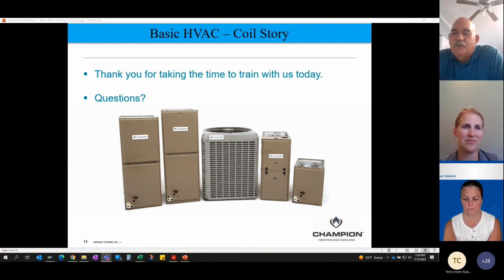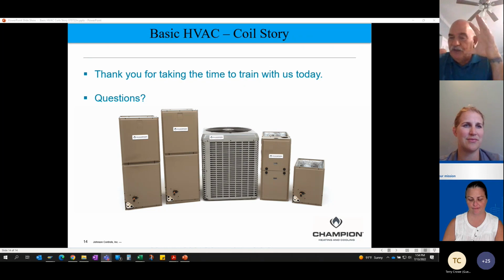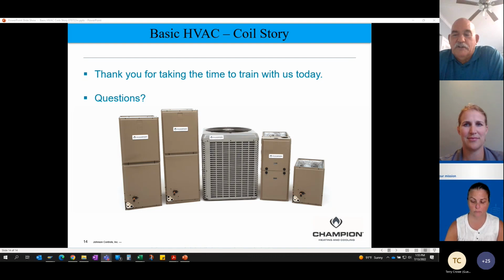Spine fin coil was invented in 1959, and General Electric started winding it on special machines down in Tyler, Texas, and they still use those machines. So this technology has been around a long time, but to their credit, spine fin is very efficient because you have a lot of surface area on those fins coming off. It is a good coil technology. The only real challenge with spine fin is cleaning it, especially if you have cottonwood or those types of particulates, real stringy or grainy things. So they've got some particularly unique applications and recommendations for cleaning spine fin. But like I said, I can't beat them up. It's a good technology. It's just a little different than what you typically see with other manufacturers.